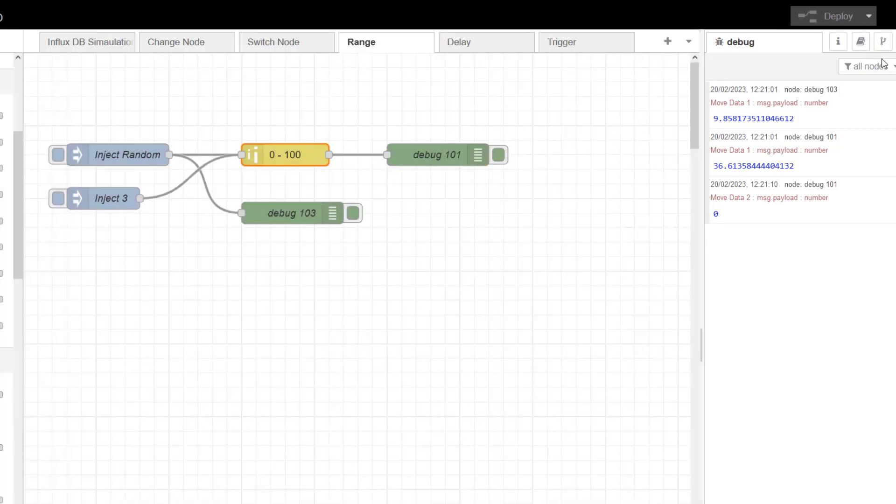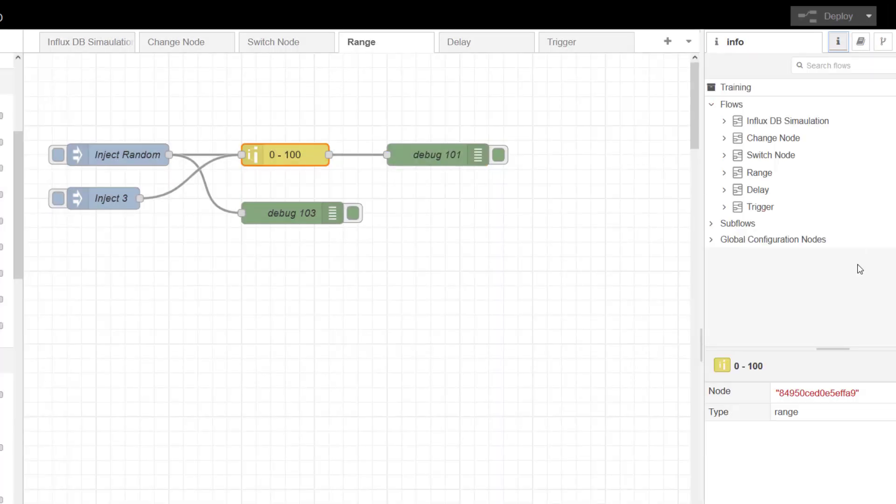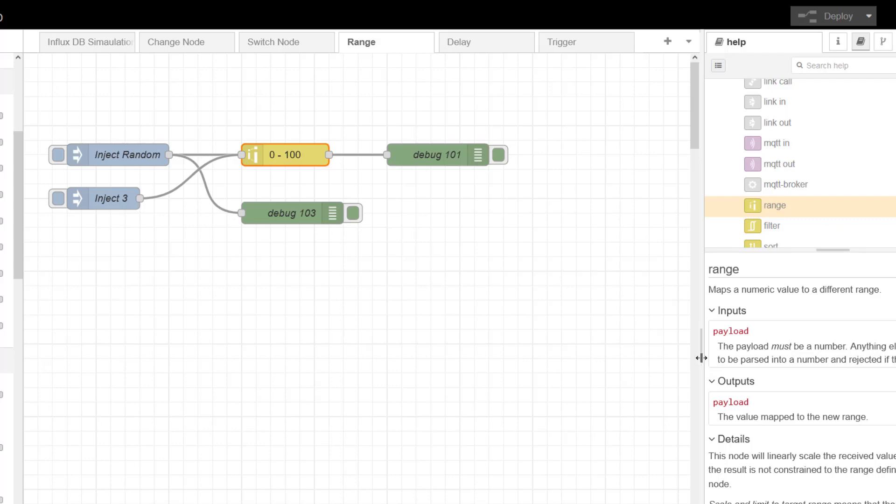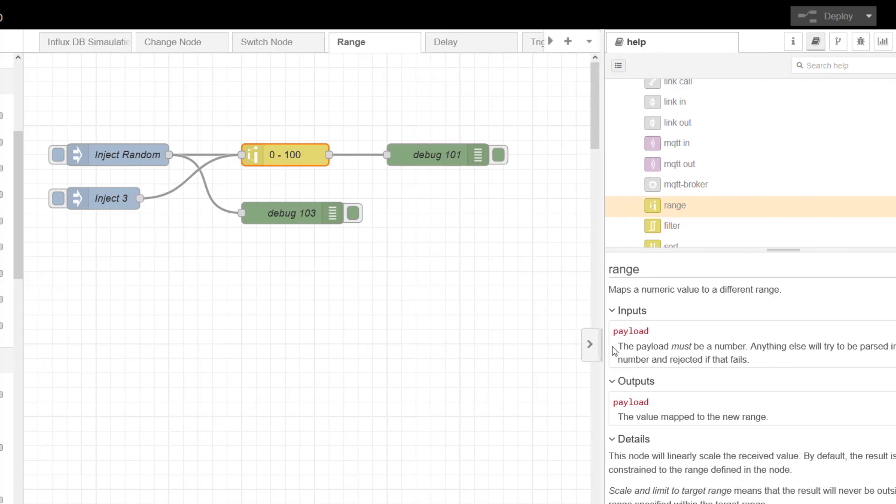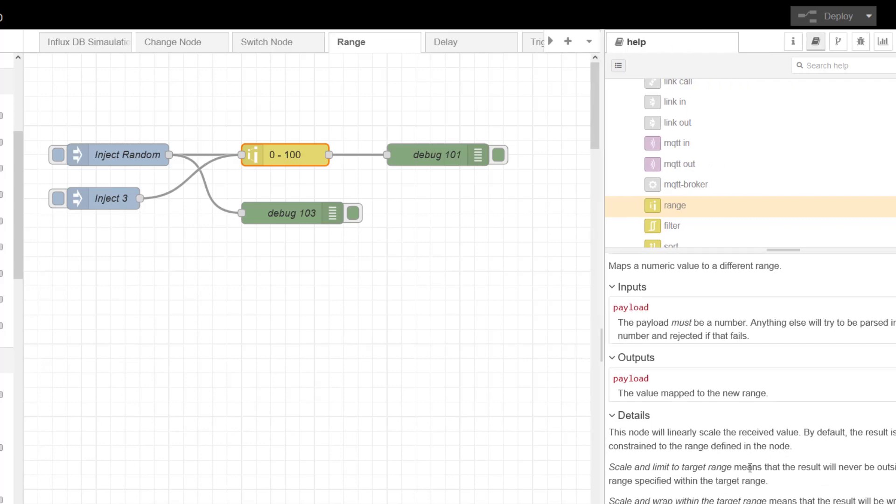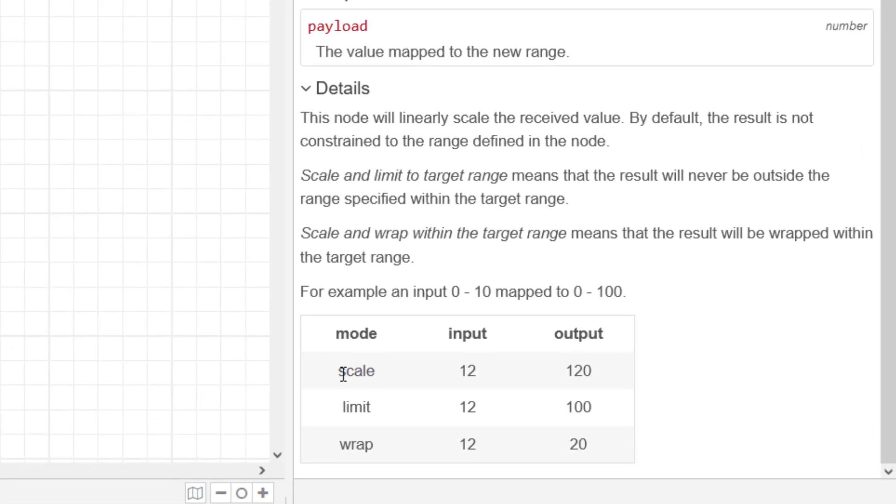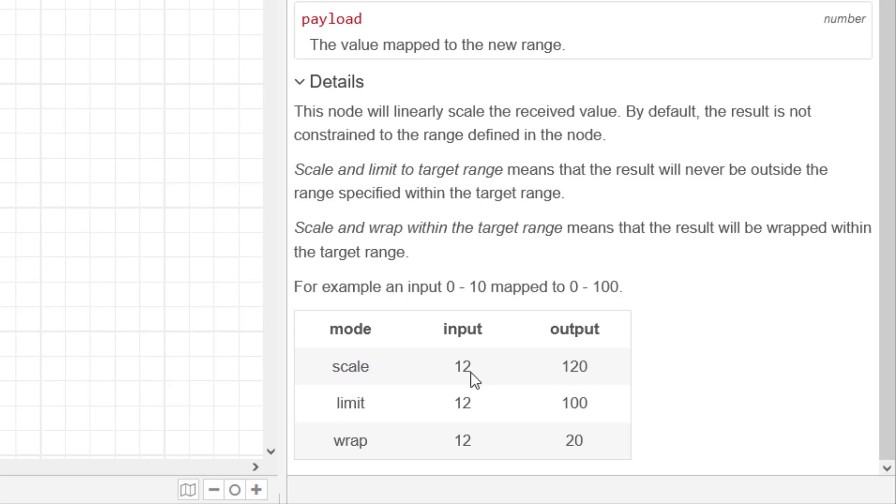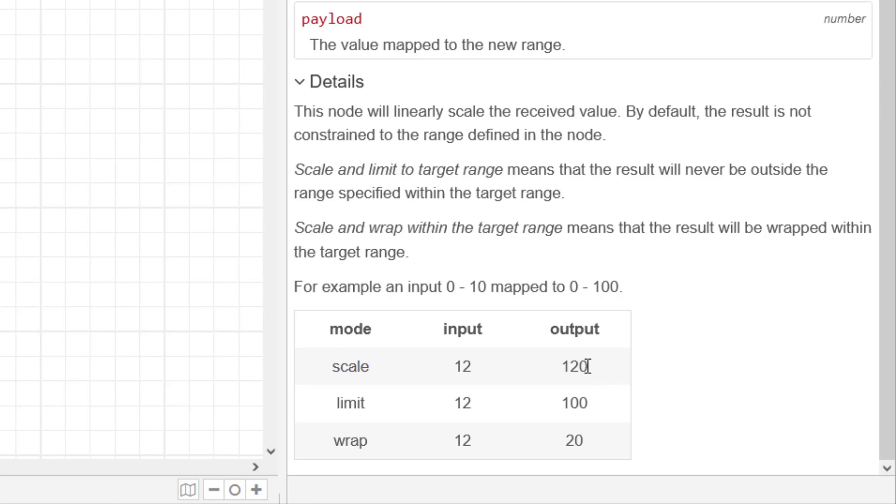I'll get the manual up for it, and then you can see it gives you some examples. So you can see here scale normally, the example 0 to 10 on the input and then output 0 to 100. So the output is the same as what we've got programmed. If you use the first method, you put a 12 in, you get 120. That's fine because it's predicting linearly where it's going to go. The one we've just done, limit, 12 it limits it at 100, and then the wrap...